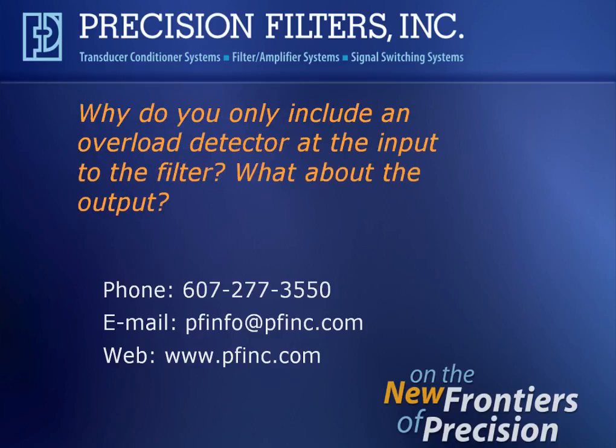Why do you only include an overload detector at the input to the filter? What about the output? When the signal is overloaded at the input to the filter, it's not often readily apparent to the user through observation of the signal at the output of the filter, since the filter does a very good job of masking that overload condition. The overload condition is very bad. It can result in zero shift in our signal. It can result in frequencies appearing in our signal that aren't really there due to the non-linearity of the amplifier when it's overloaded. So as a measure of data validity, it's important to know that the input to the filter is not overloaded. And that is why we always put an overload detector at the input to the filter.